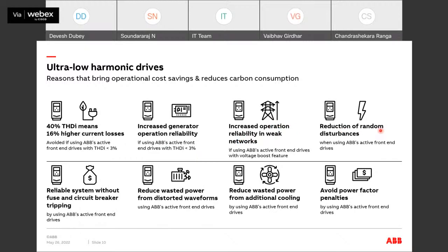Reduction on the random disturbance if we are using active front-end drives. Reliable system without circuit breaker tripping by using active front-end drives. We can have reduced wasted power from the distorted waveform. There is a reduced wasted power from the additional cooling fans, and from additional equipment like a chopper or a resistor for dissipating the power, that can be avoided.